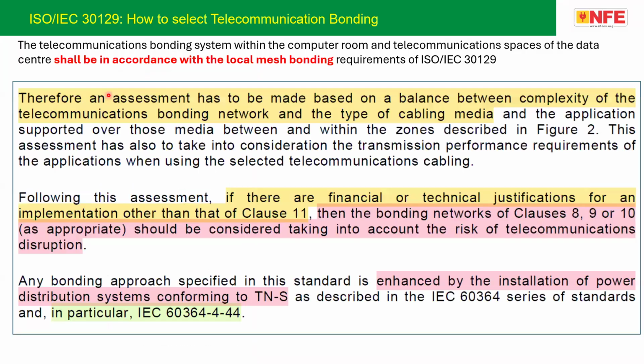Clause number 6 of the standard explains selection of telecommunication bonding network. What the standard says is, the designer should make an assessment. Therefore, an assessment has to be made based on a balance between complexity of the telecommunication bonding network and the type of cabling media. Following this assessment, if there is financial or technical justification for an implementation other than clause 11, then the bonding network of clause 8, 9, and 10 as appropriate should be considered. So what the standard says is you must prefer the recommendations in clause 11. If you have any technical or financial justification, then you can go for the recommendations in the other clauses, which are 8, 9, and 10.